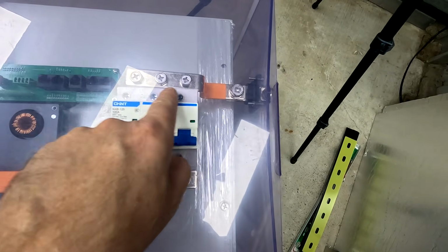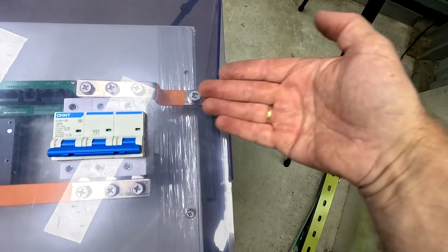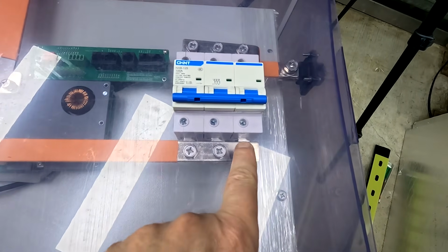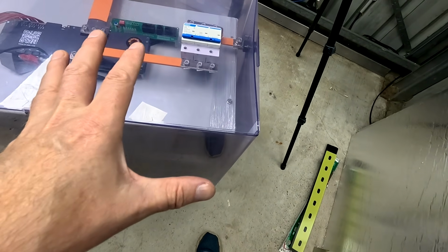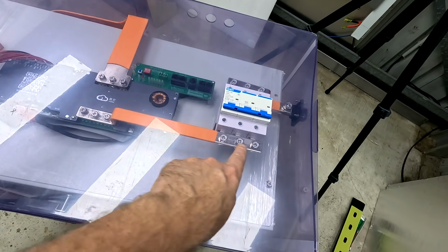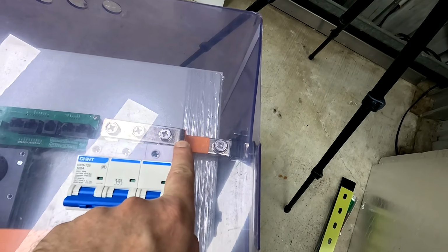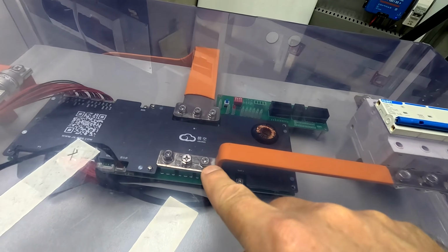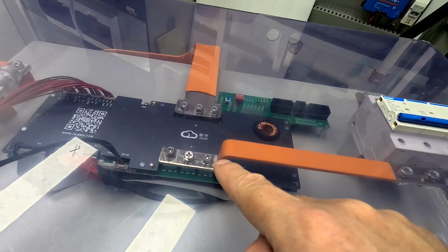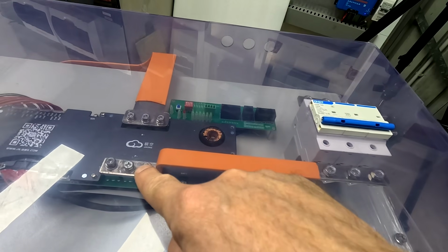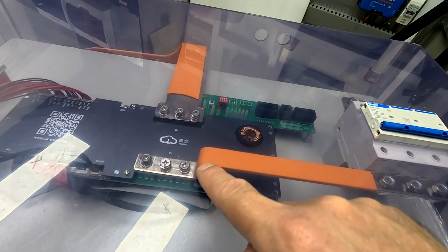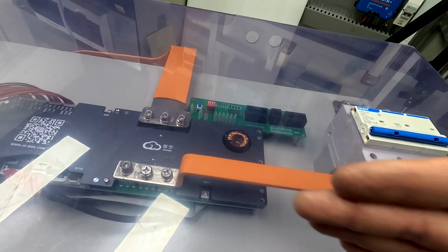But then when I tighten everything, it pulls on this side, and we clearly cannot leave it like this. So something is not quite lining up, and I think it's this bus bar which is a bit too long, and the same for this other bus bar, a bit too long. I guess that's why other manufacturers use flexible bus bars for that. If this bus bar were flexible at these two bends, I could easily move it between the circuit breaker and the BMS, and this part would just compensate for a couple of millimeters.